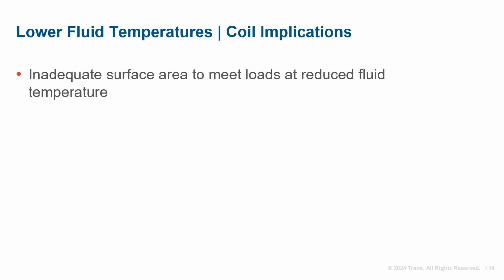Often the first thing we get asked when an engineer is faced with an electrification project is, how hot can you make water with a heat pump or chiller? But we need to think more holistically. With reduced hot fluid temperature, coils may not have adequate transfer surface to make the original supply temperature. When this is the case, action must be taken at the coil level.